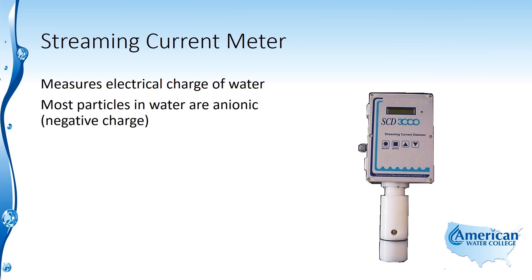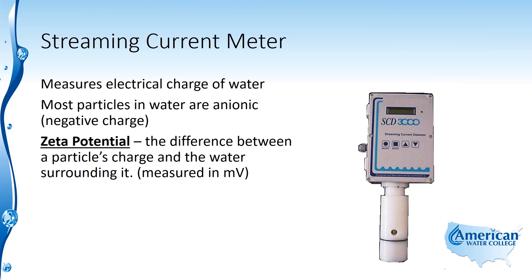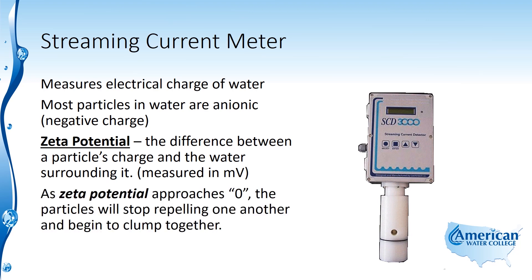Most particles in water are anionic, which means they carry a negative charge, and that's the zeta potential. The zeta potential is the difference between a particle's charge and the water surrounding it, and the units for zeta potential are millivolts. As zeta potential approaches zero, the particles will stop repelling one another and begin to clump together. So we want the zeta potential to approach zero, or the magnitude of the negative charge to get smaller and smaller, so that flocculation can occur.